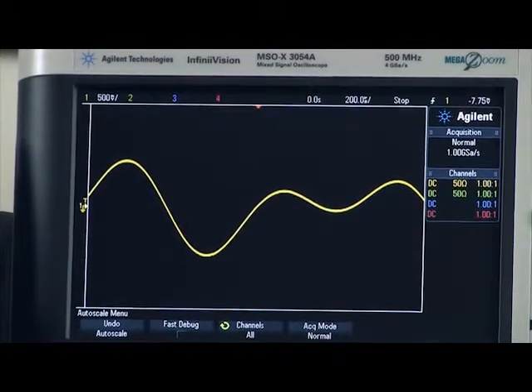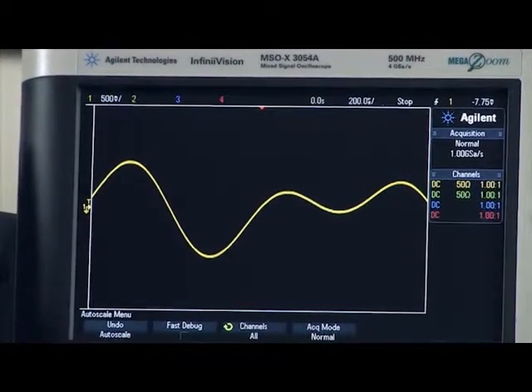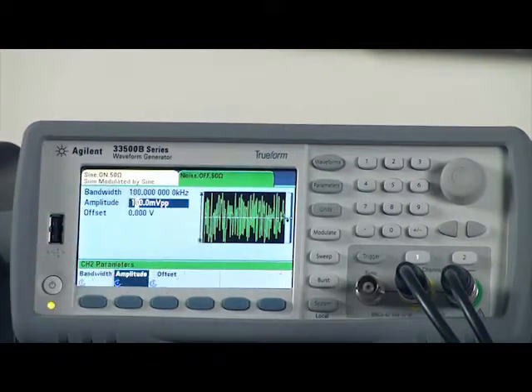Now let's put some additive noise onto here. We do that by using channel two. We'll turn on the noise. The noise is set at 100 millivolts peak to peak. That's at about 10% of where the dual-tone is. So let's leave it there to start with.